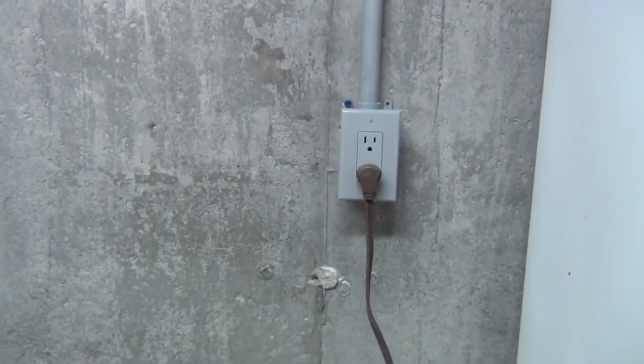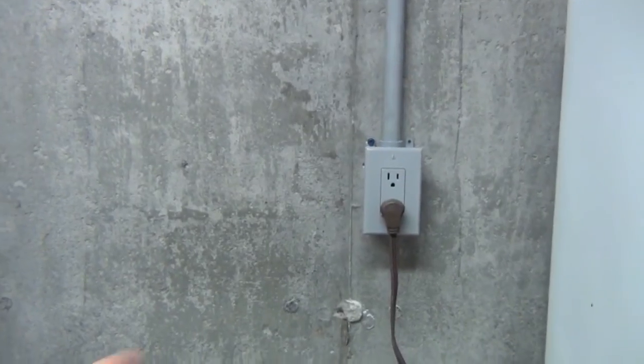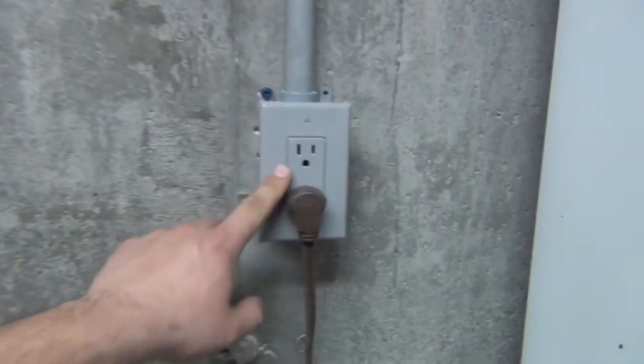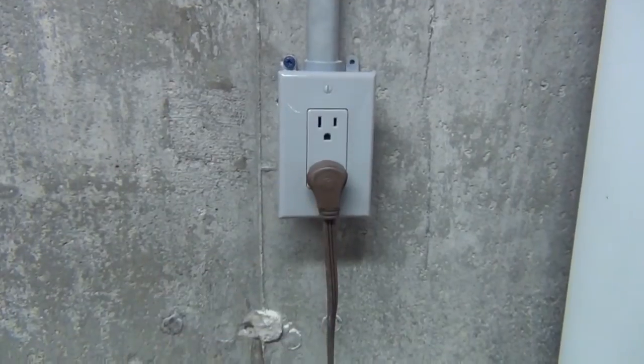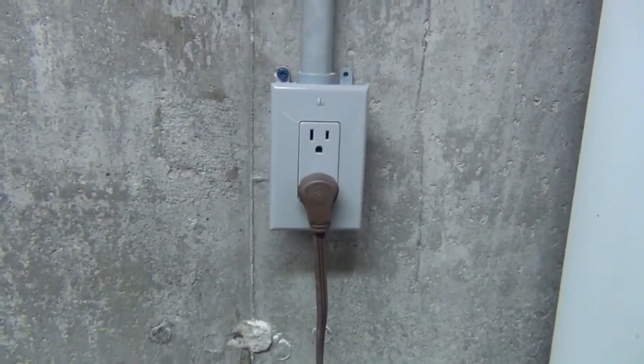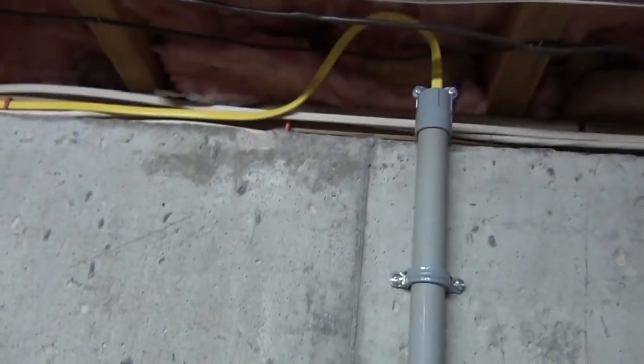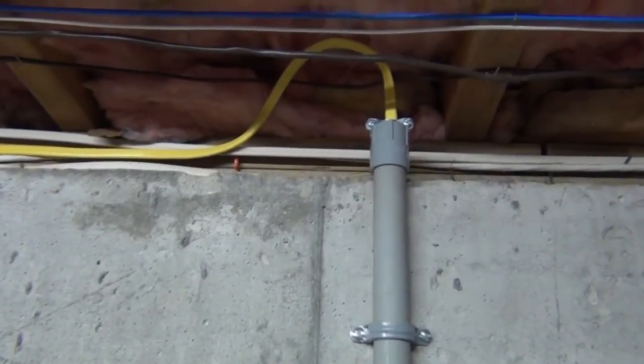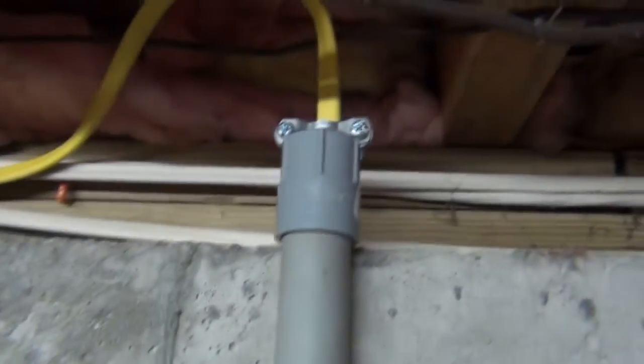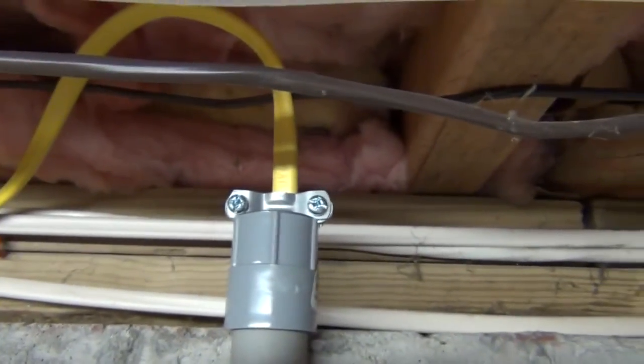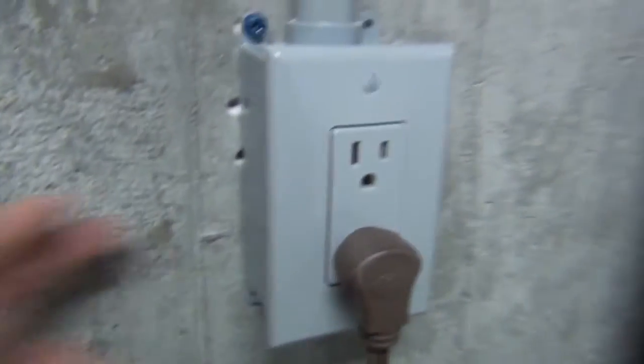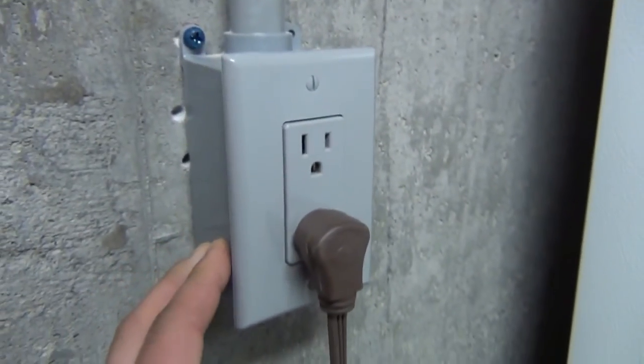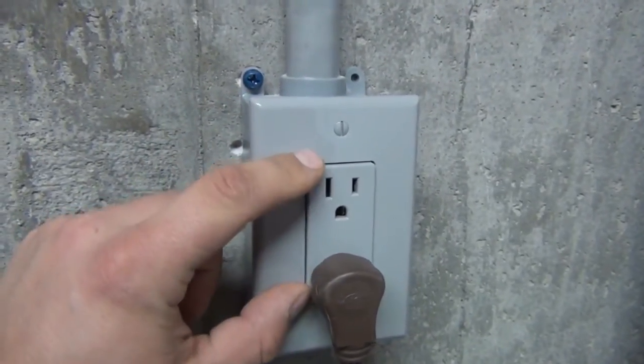Basically, it's a 20 amp home run circuit, this is the only receptacle on this line, a cord here feeding the freezer. It has a 20 amp circuit, it has 12 gauge wire, as you can see up here, the yellow Romex. I got a three-quarter plastic conduit mounted on the wall here. It's got your Romex connector on top there. I got a threaded coupler to slip it onto the three-quarter conduit coming down here, down to a box that I mounted on the concrete with a duplex outlet.